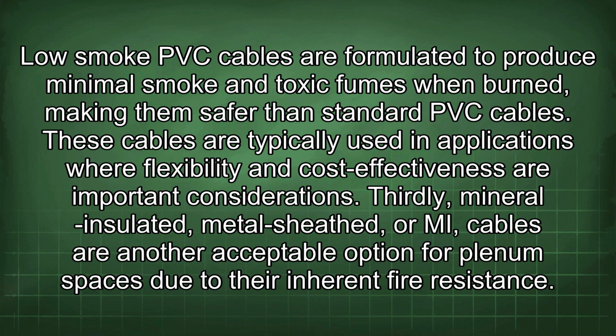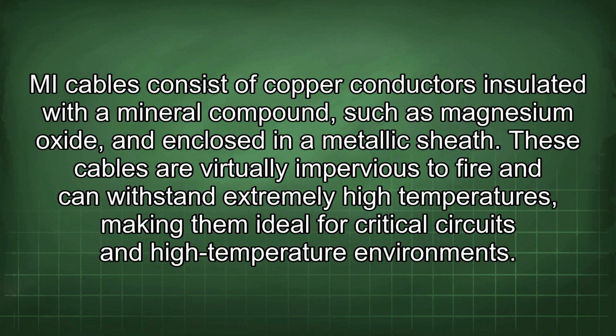Thirdly, mineral-insulated metal sheath, or MI, cables are another acceptable option for plenum spaces due to their inherent fire resistance. MI cables consist of copper conductors insulated with a mineral compound, such as magnesium oxide, and enclosed in a metallic sheath. These cables are virtually impervious to fire and can withstand extremely high temperatures, making them ideal for critical circuits and high-temperature environments.